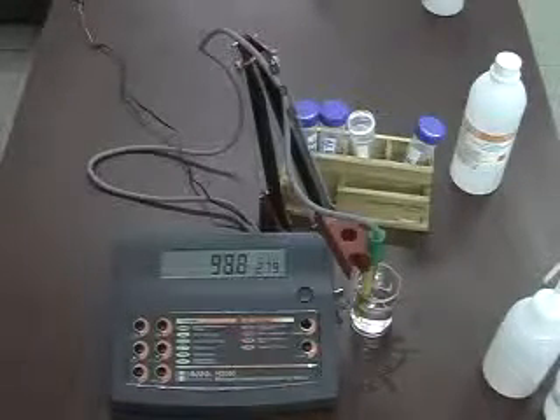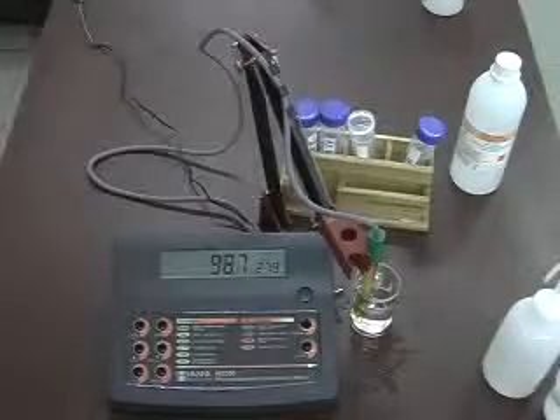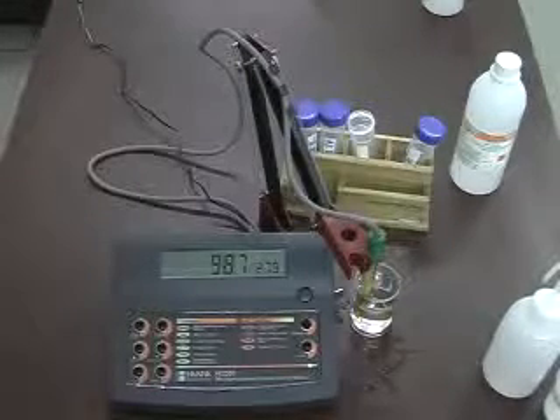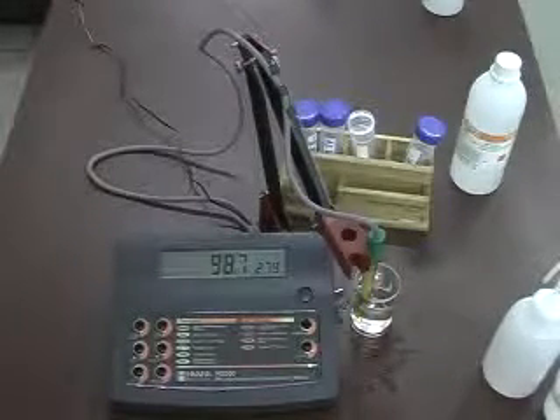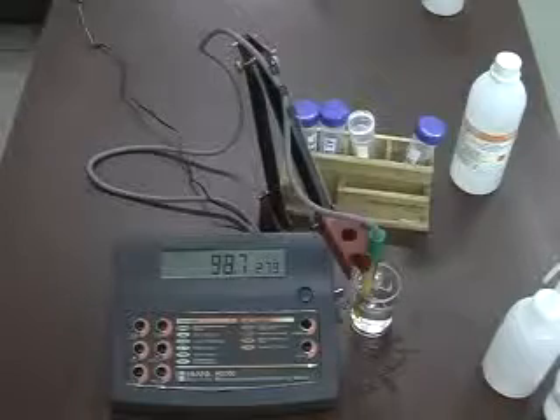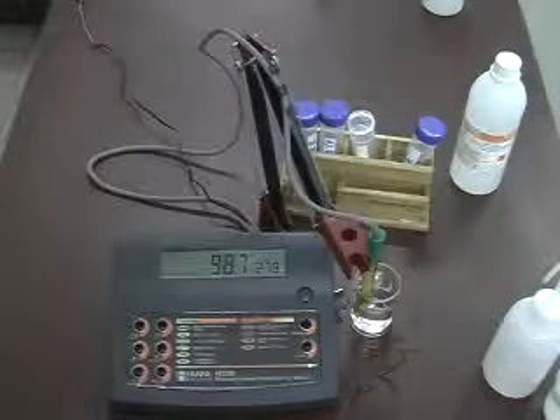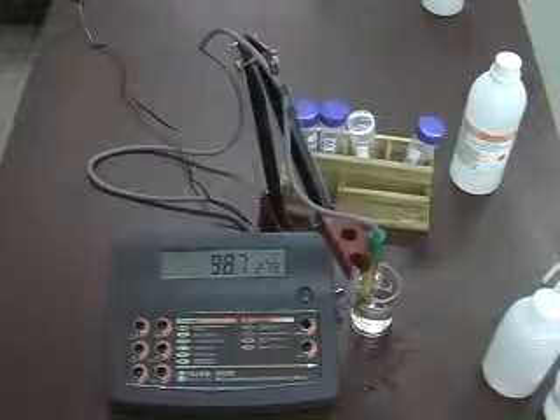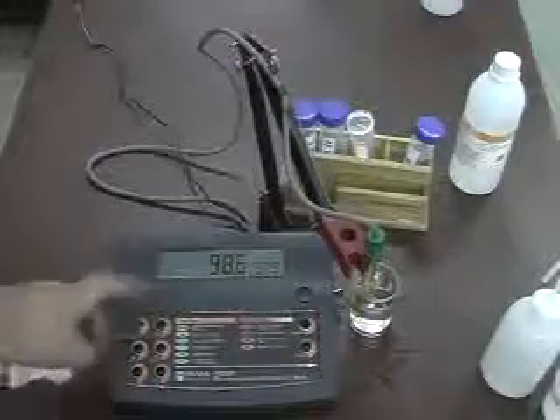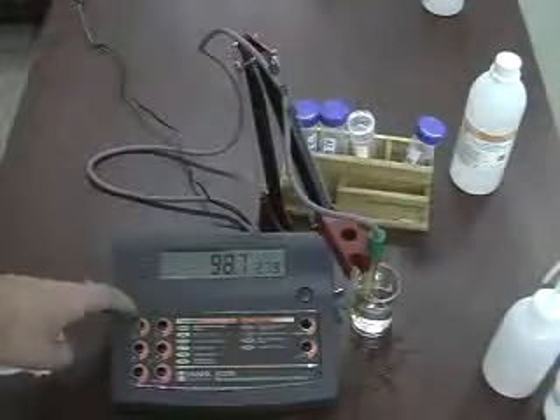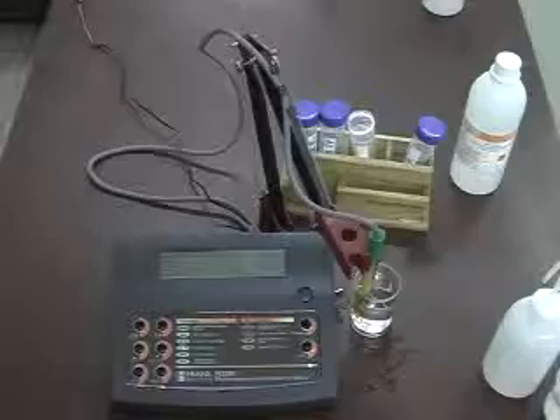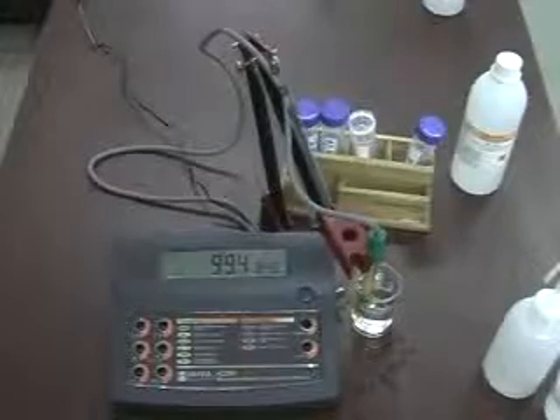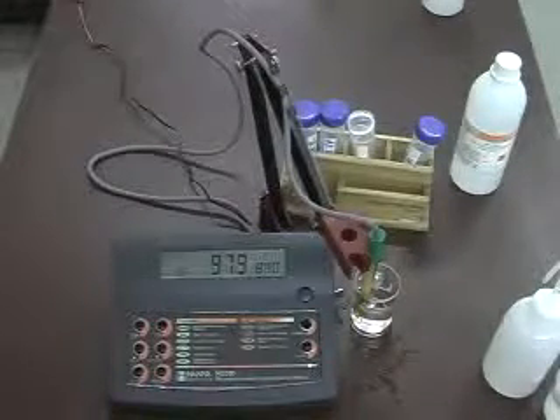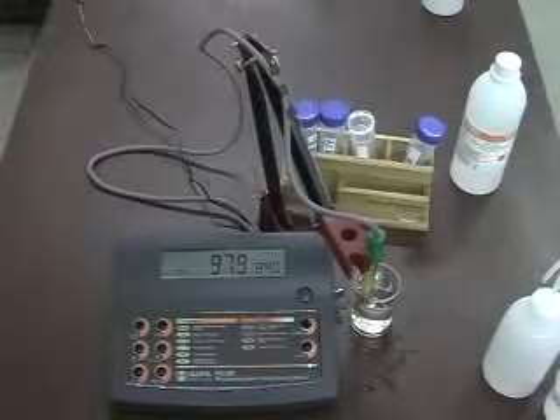Again, these are two different standards I would use based on an application. If I'm going to be measuring water, high purity water, reverse osmosis, the lower range conductivity measurements, I should be calibrating in the 84 microsiemens solution. And I can tell the meter that, hey, this is 84 microsiemens solution by simply pressing the cal button. It's prompted me for 84 microsiemens solution. After it sees a stable measurement, it will lock on that measurement and we will hit confirm again.